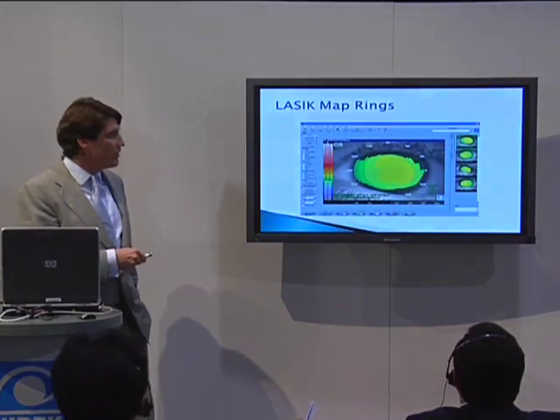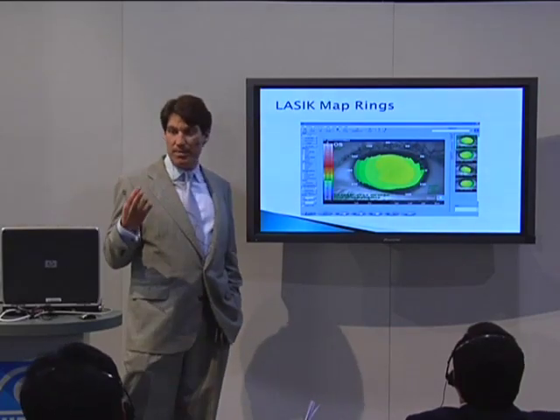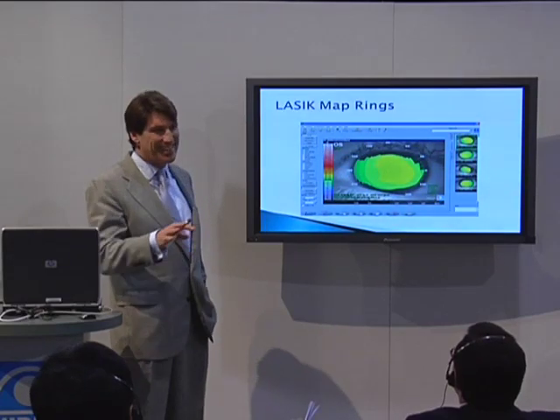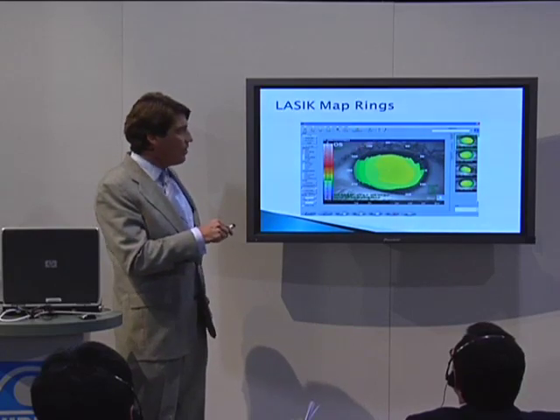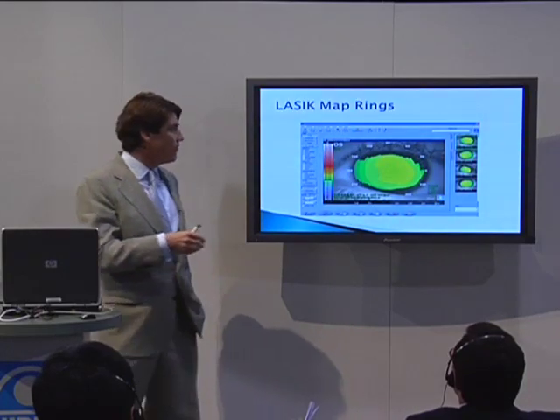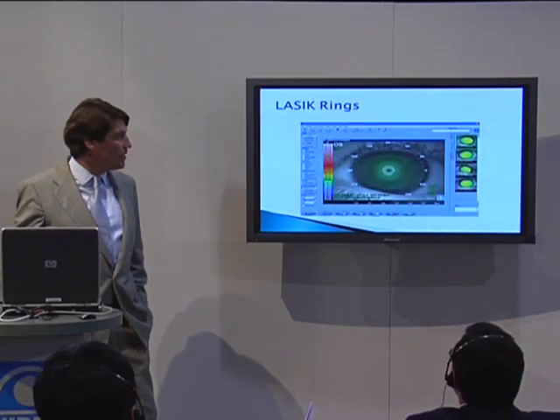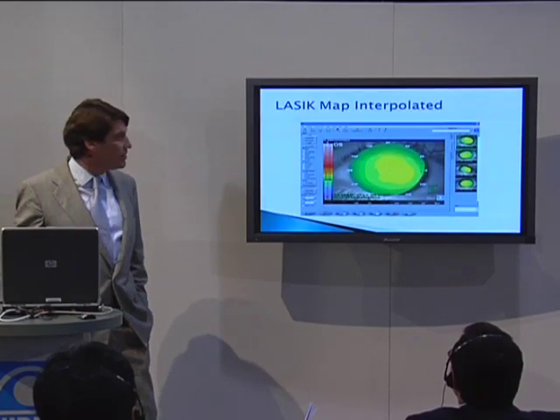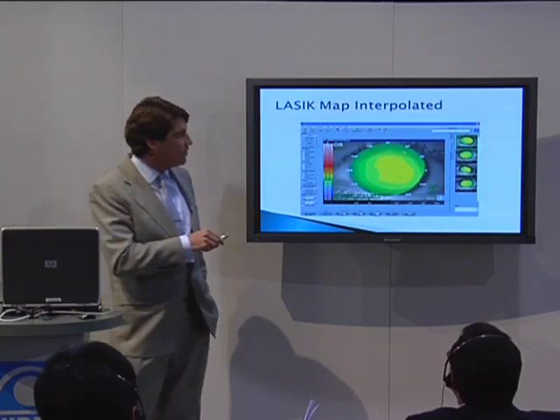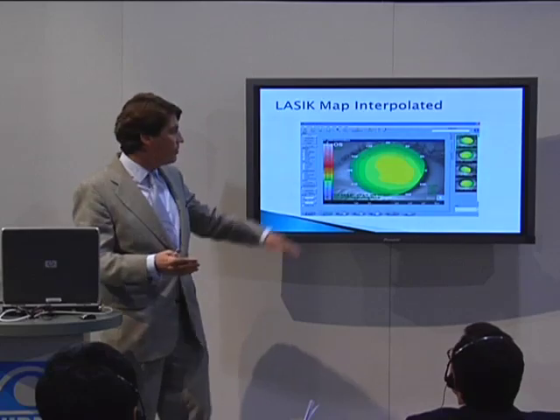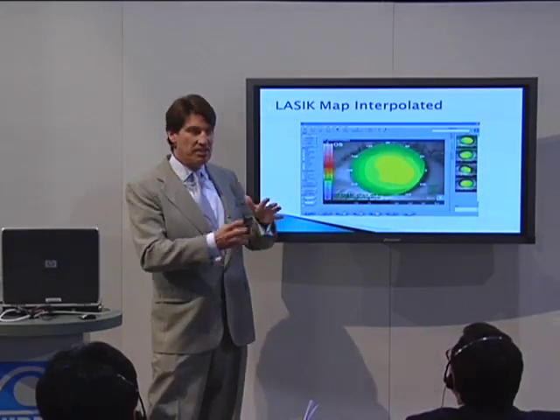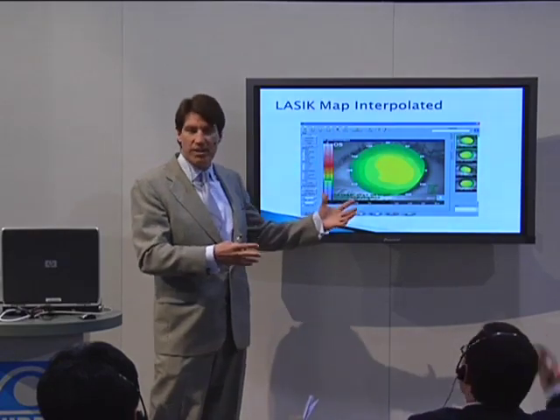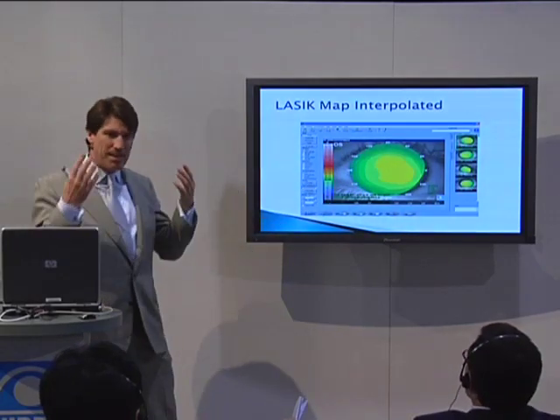You can also look at the actual raw data. If you want to see what's being interpolated into the computer, you can modify those rings — remove artifacts from a nose shadow or a lid shadow. Here are the rings themselves that you can literally go in and modify. Then there's an interpolated map that shows you what data was put into the map — what the computer weight-averaged — so you can see what it looked like even if you didn't get a good image. If it doesn't make sense, you can take another map or keep it.